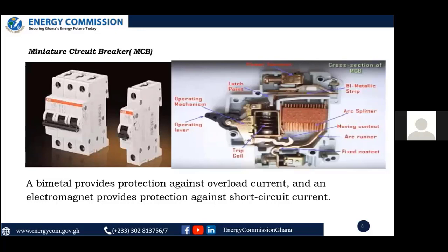And what will cause an overload current? The engineers on the platform here will bear this out. There's something we call voltage surges, voltage dips, voltage fluctuations. They are all power system disturbances. They can all cause this miniature circuit breaker to trip. When you have a surge in the voltage, once the voltage has increased, you are likely to have an increase in current. That can happen for just a short period. So once it trips, and the fault has been rectified, sometimes by the distribution company supplying the voltage, or sometimes from your load side, then you can trip it back to the on state.